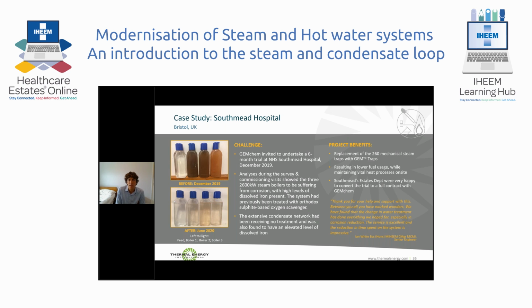Recently, we were challenged by Southmead Hospital, who were struggling with iron levels within their system to prove the effectiveness of this treatment over 6 months. You can see here the condensate samples collected from the 3 boilers and the condensate return before the feed water. There's a clear sample. The 3 boilers before the treatment was started, and then visually you can already see the difference.